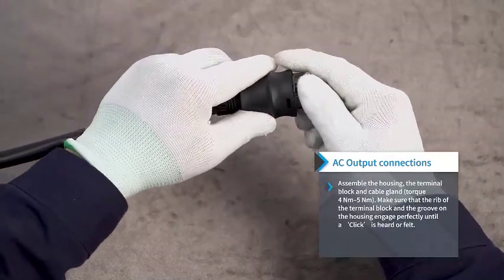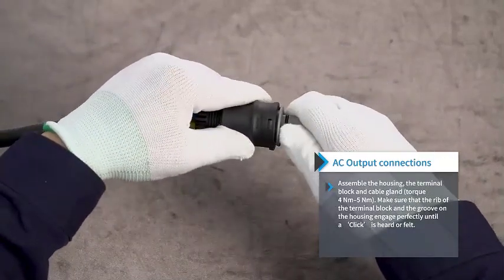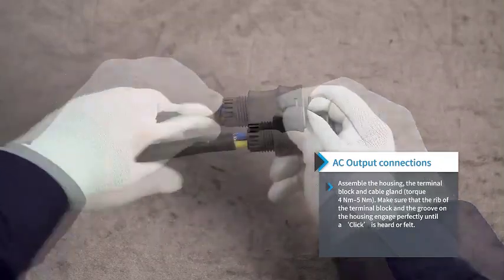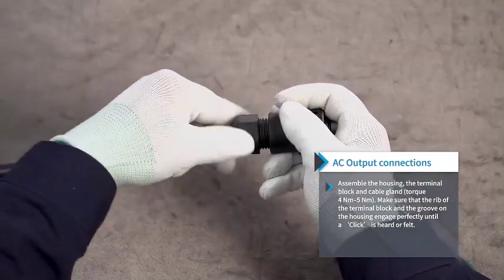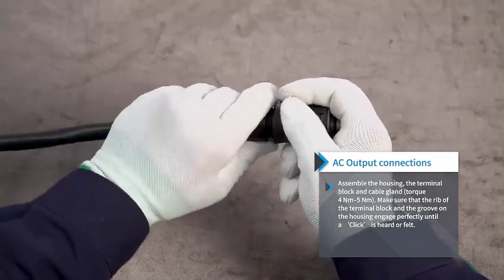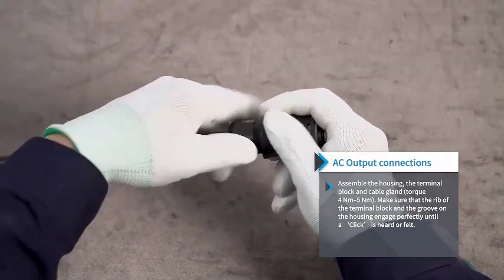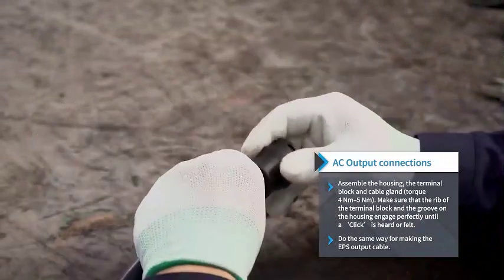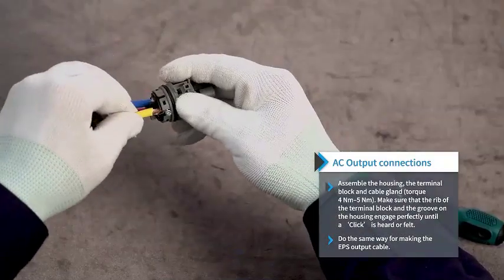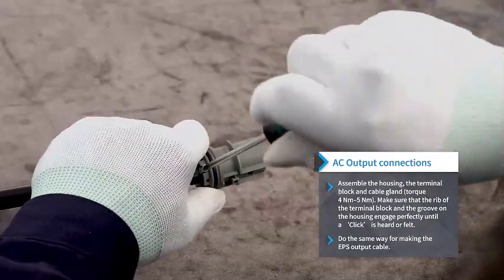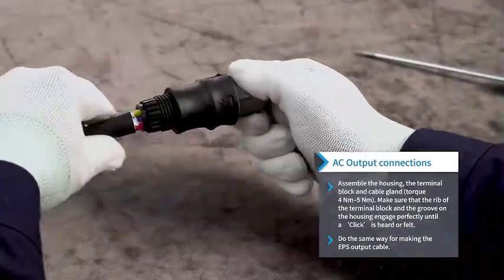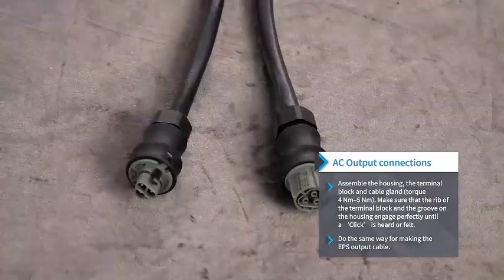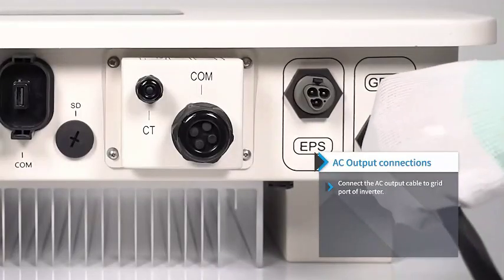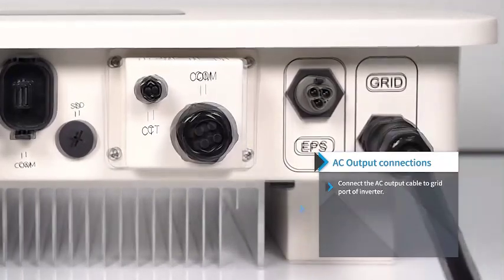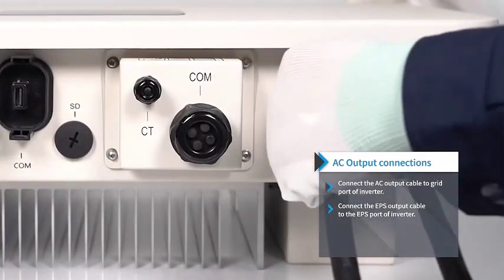Assemble the housing, the terminal block, and the cable gland. Torque 4 Nm to 5 Nm. Make sure that the rib of the terminal block and the groove on the housing engage perfectly until a click is heard or felt. Do the same way for making the EPS output cable. Connect the AC output cable to the grid port of the inverter. Connect the EPS output cable to the EPS port of the inverter.